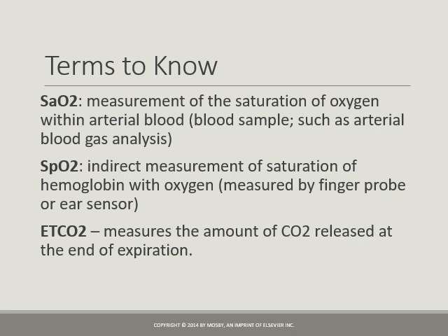I saw it as a more favorable way to measure. It's called EtCO2 or end-tidal CO2. So the person exhales, and then a beam of infrared light is passed over the gas sample on a sensor. And the presence or lack of CO2 is inversely indicated by the amount of light that passes through the sensor. So, if the CO2 is high, you'll get a low infrared signal, and a low CO2 yields a high amount of light. So we want to know how much is coming out.